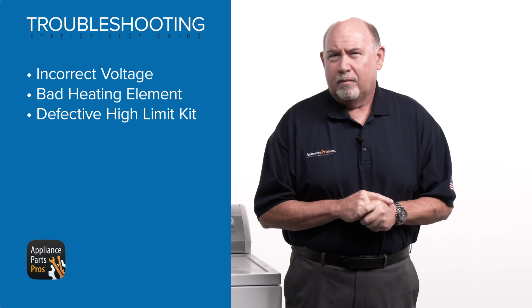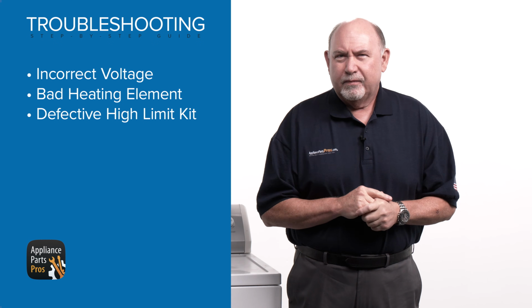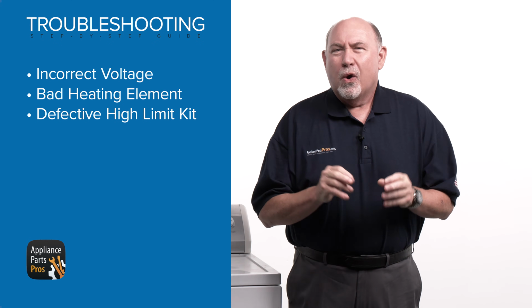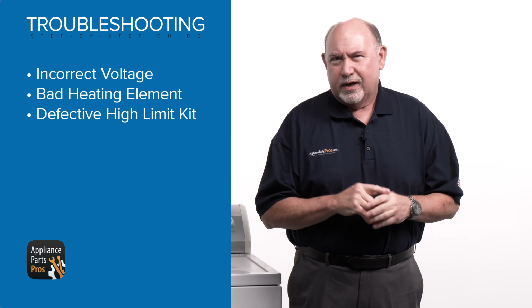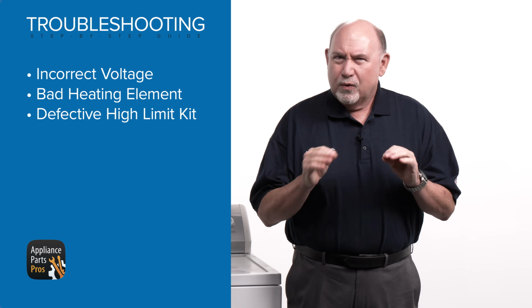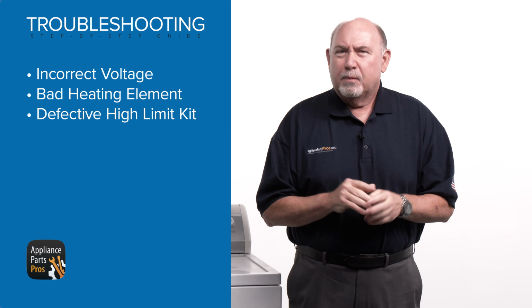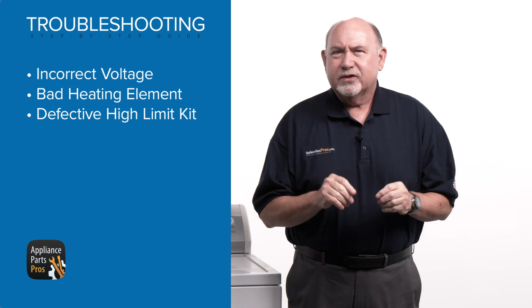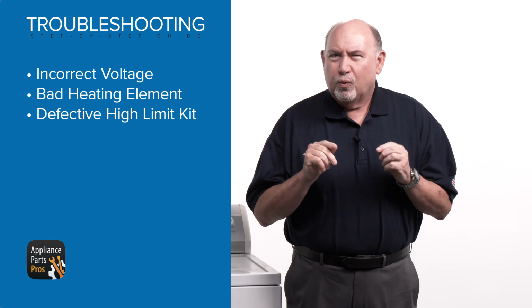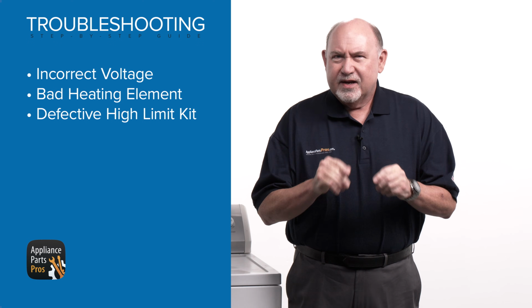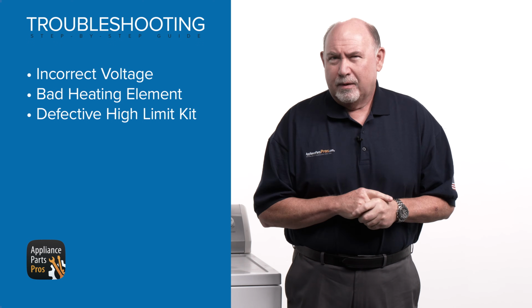There were typically 3 common areas that caused the problem: incorrect voltage, a bad heating element, or a defective high-limit heater kit. Of course, there are a few other rare situations, but for the most part, these areas are the most common. Let's work together to identify and fix this problem step by step.